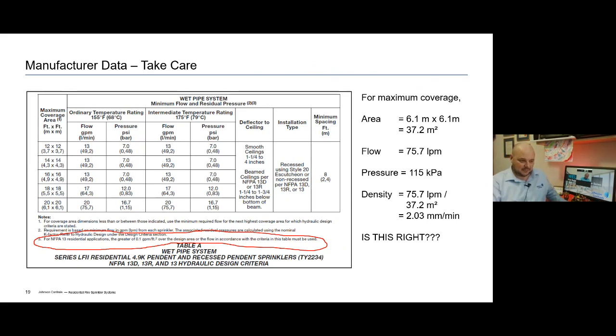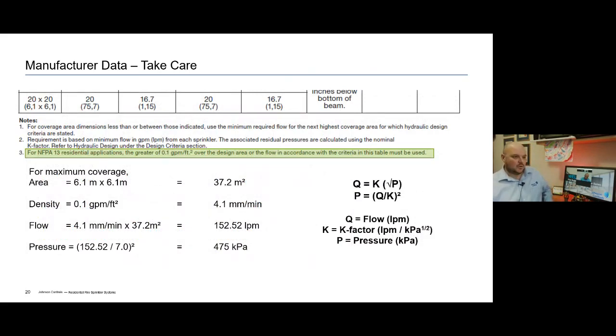What does that mean? What that means is that under Australian standards, and also New Zealand standards, we need to allow 4.1 millimeters per minute per square meter over that 37.2 square meters. If I work out the pressure requirement for that, it's not 115 kilopascals, it's 475 kilopascals.